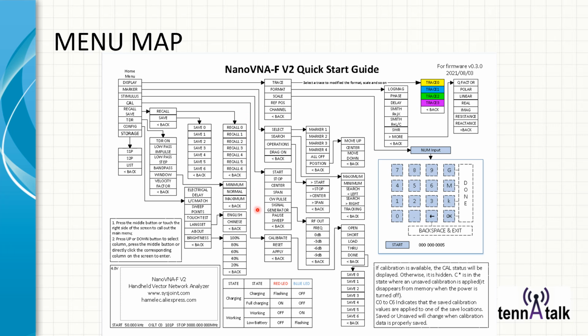Okay, so let's take a look at the calibration. You reset and then you go to calibrate. When you calibrate, it'll ask you to place an open on the SMA connector on port 1, and then you remove that and apply the short and press the short button. Then you take that off and apply the load, the little load device, screw that on, press load. If you're doing through calibrations for log mag, you also put your cable, just a short cable, one of the ones they provide, from port 1 to port 2, click on through, click Done. After that you can select which of your calibration storage slots, presets, you can save it to, because then later on you can recall those without having to recalibrate.